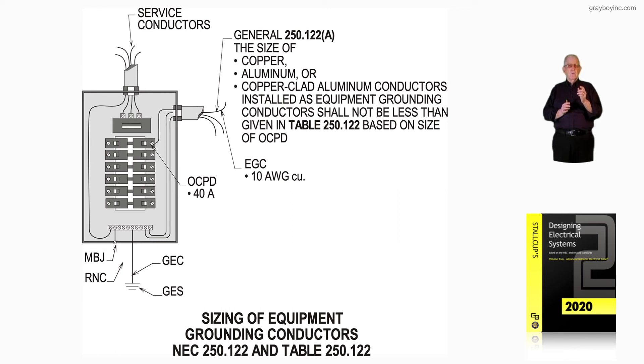We'll use the four-aught to stay on the same page. A number four-aught conductor requires a number two grounded conductor, as seen in the service equipment. A main bonding jumper, if it was a conductor, would be number two. And the grounding electrode conductor would be number two if it connected to structural steel or a metal water pipe, in accordance with 250.66.